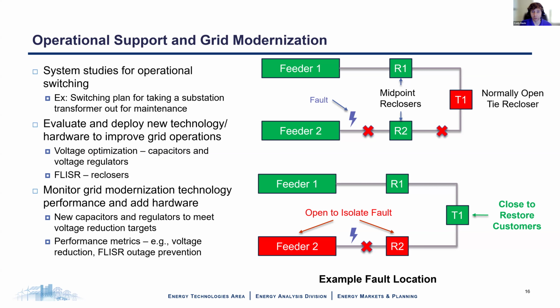So what FLISR is going to do is identify that the area between R2 and T1 is out, but there's no fault there. So I can actually take that R2 recloser and open it, and now I've got my fault isolated between the feeder 2 exit and that R2 recloser. And now I can close T1 to re-energize all of those customers between T1 and R2. So the idea is those customers are out because of an upstream issue, but we can reconfigure the system to get them back on without having to make any repairs. And it dramatically increases the speed of restoration to at least some of the customers who are impacted, which is awesome.